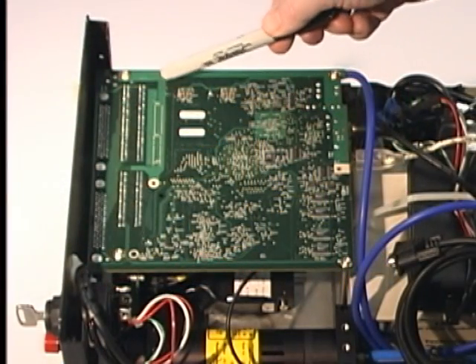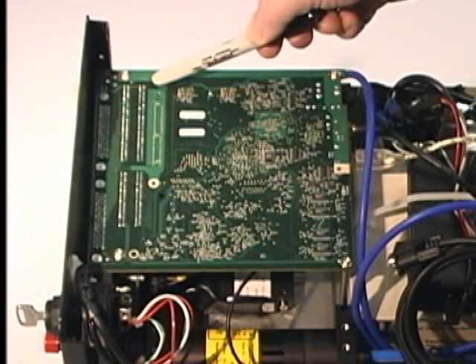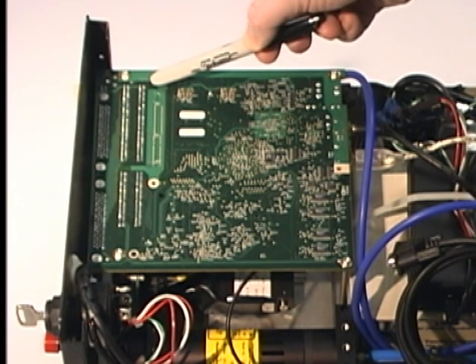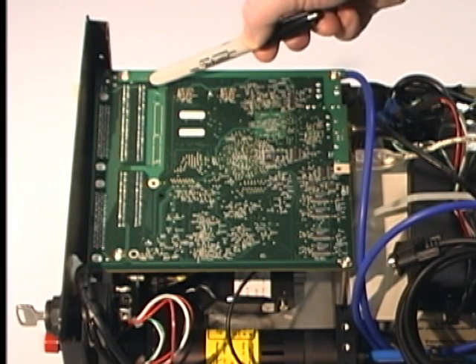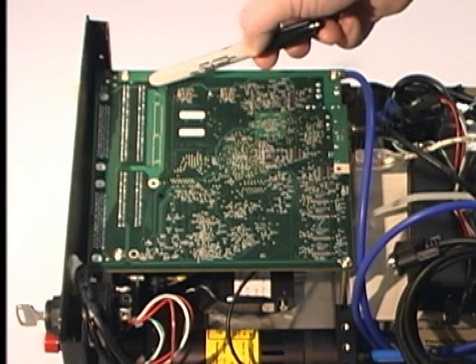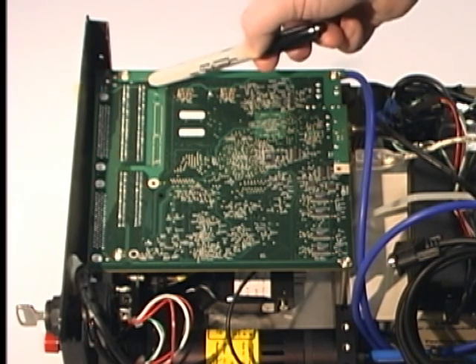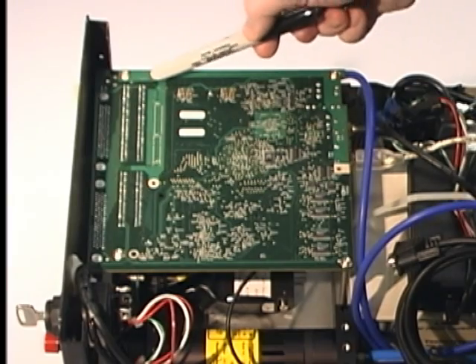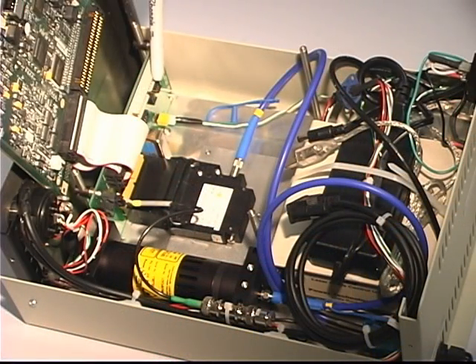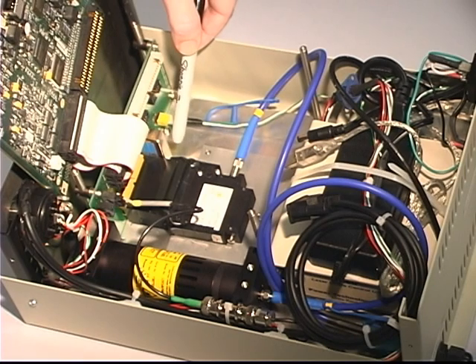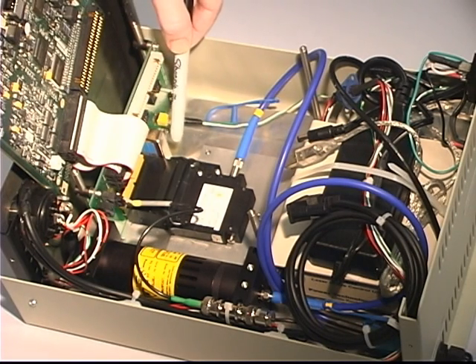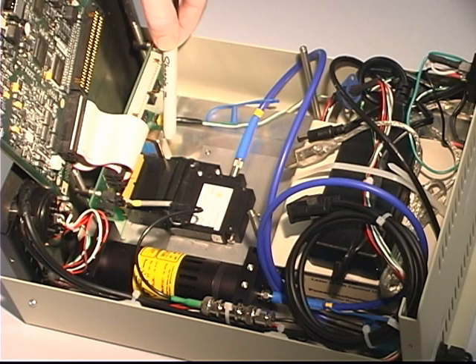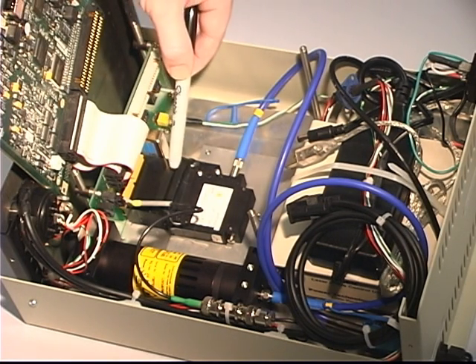The analog-to-digital converter in this case is a commercially available unit from National Instruments. It performs 12-bit digitization at rates up to 1.2 MHz and is used to both supply the modulation waveform to the diode laser power supply, as well as digitize output from the detector electronics and direct LIF information to the laptop for processing. A 32-channel linear array photomultiplier tube, or PMT, is used to detect the optical output of the spectrometer. For this application, a PMT is ideal due to its high gain and bandwidth characteristics.